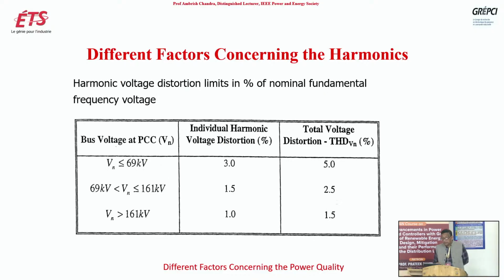Now see this table. Harmonic voltage distortion limits in percent of nominal fundamental frequency for harmonics less than the 50th harmonic. This is new. Earlier this was not there in IEEE Standard 519-1992, but I think they have recently added it. Otherwise, for bus voltage at PCC less than or equal to 69 kV, the individual harmonic voltage distortion limit is 3%, and total THD should be less than 5%. We already know this, right? You are already using it in the lab.